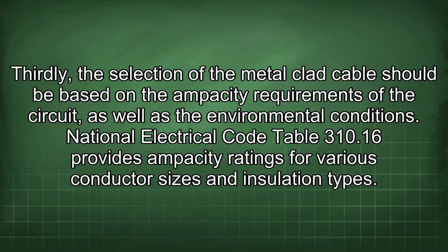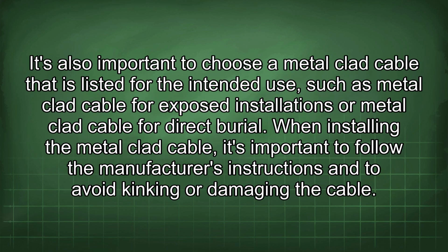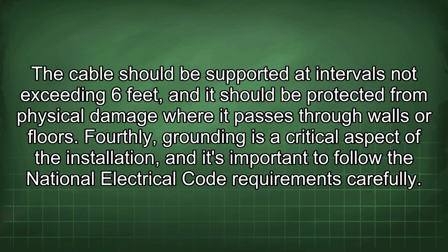Thirdly, the selection of the metal-clad cable should be based on the ampacity requirements of the circuit as well as the environmental conditions. National Electrical Code Table 310.16 provides ampacity ratings for various conductor sizes and insulation types. It's also important to choose a metal-clad cable that is listed for the intended use, such as metal-clad cable for exposed installations or metal-clad cable for direct burial. When installing the metal-clad cable, it's important to follow the manufacturer's instructions and to avoid kinking or damaging the cable. The cable should be supported at intervals not exceeding 6 feet, and it should be protected from physical damage where it passes through walls or floors.